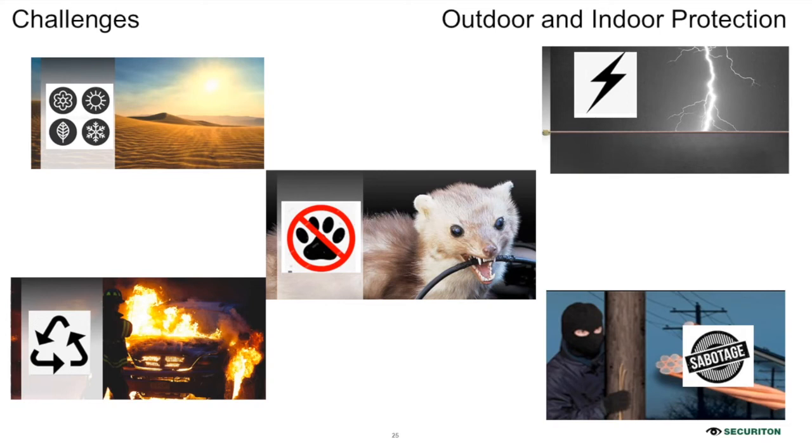steal or whatsoever, and any detections in the real situation, if there is a cut in this copper tube or stainless steel, the ADW will perform a cycle check to see whether there is a leakage or breakage, and gives you a fault immediately within the period of 5 minutes. Less than 5 minutes, it should be able to give you. This is also according to the EN 54-22 rules as well.